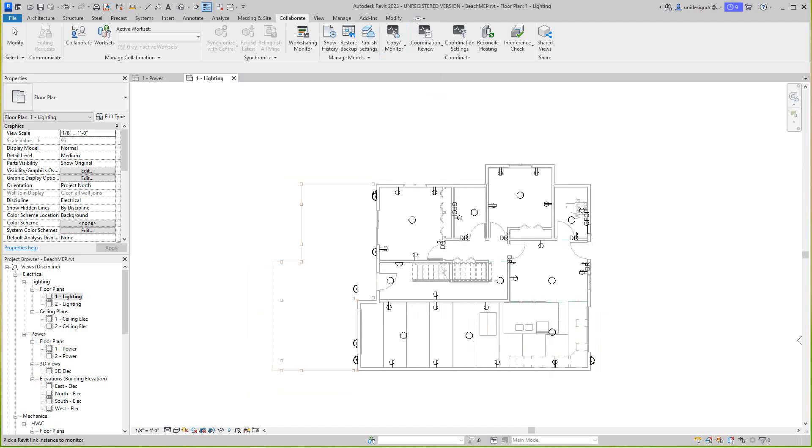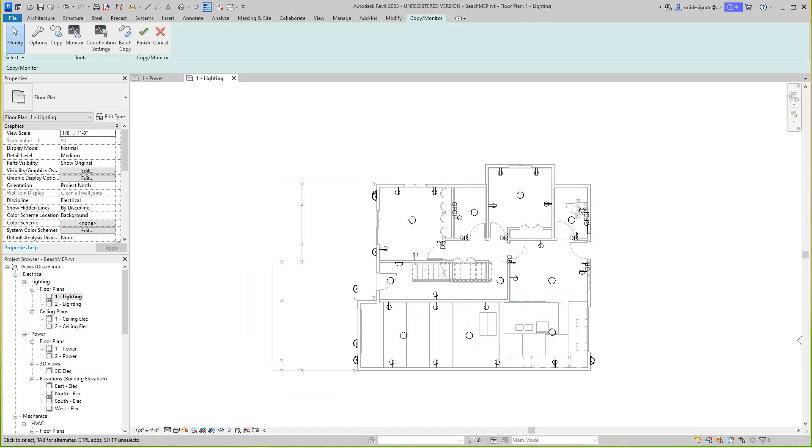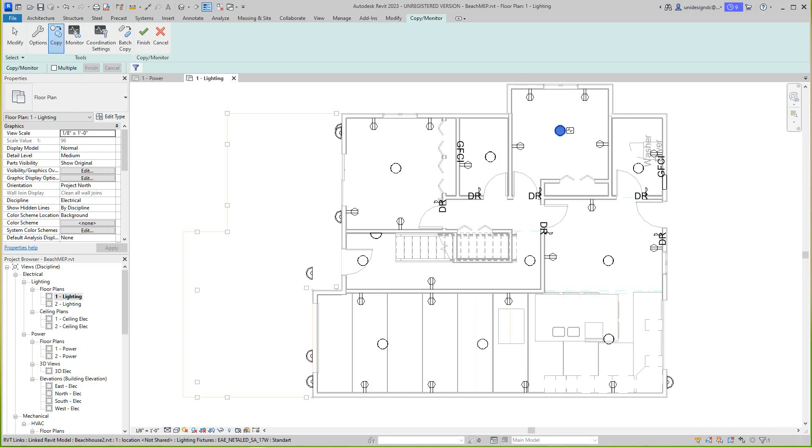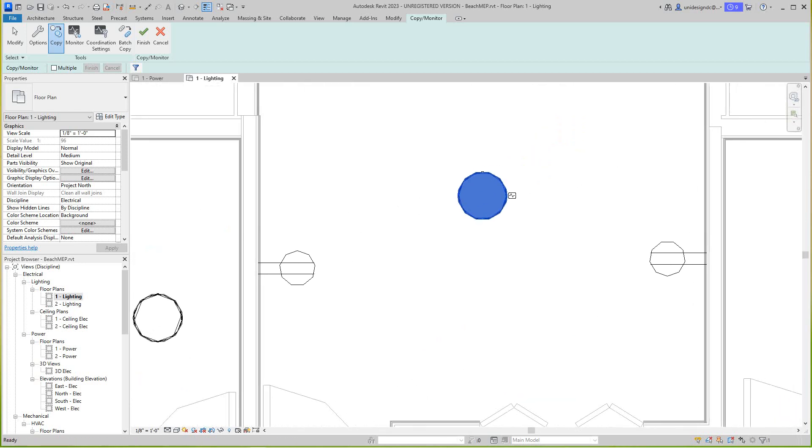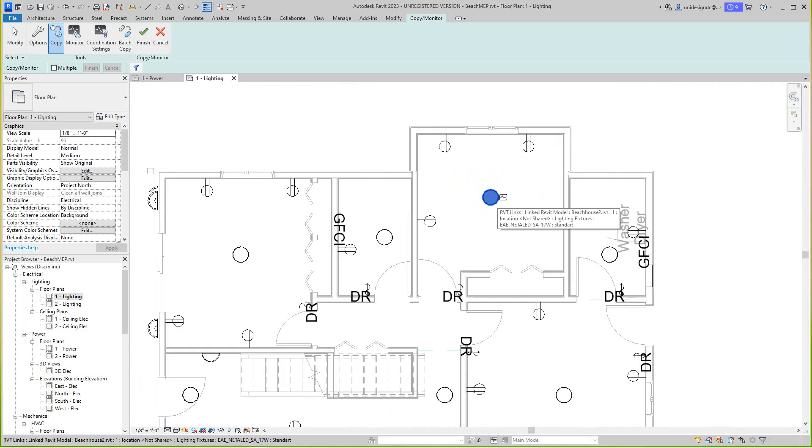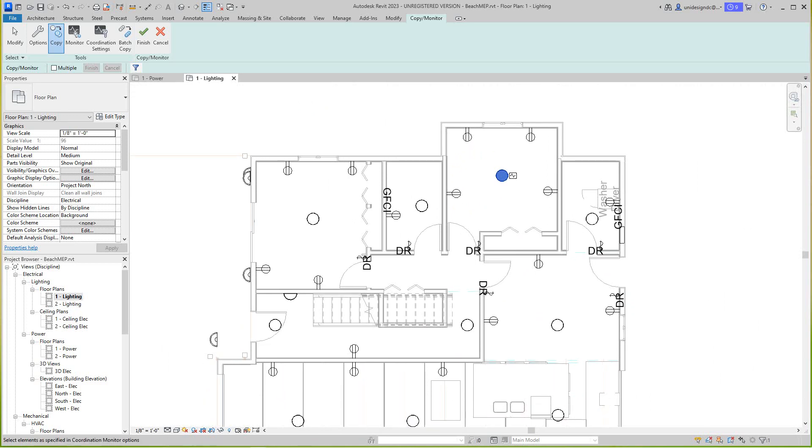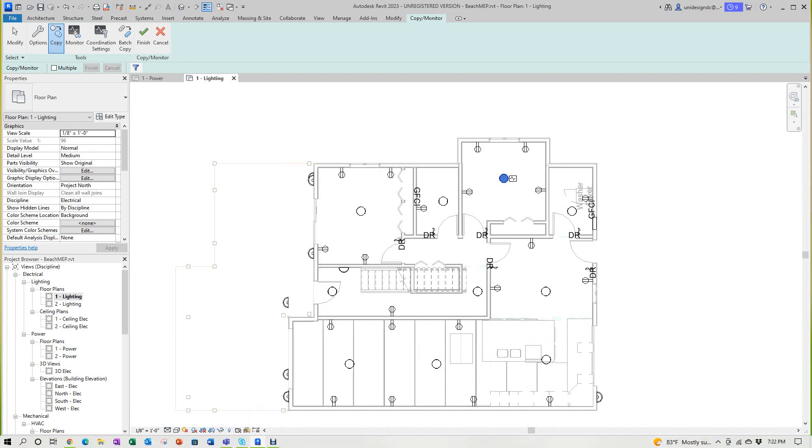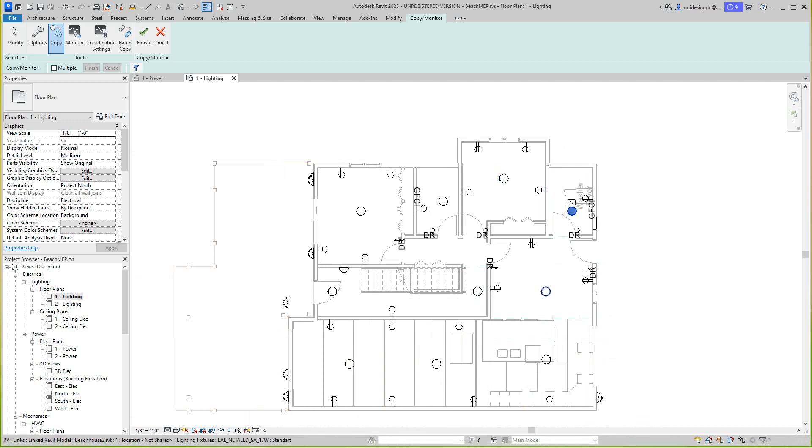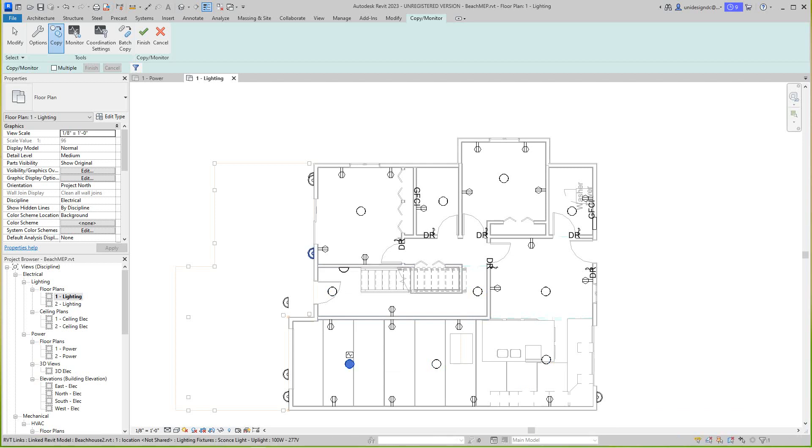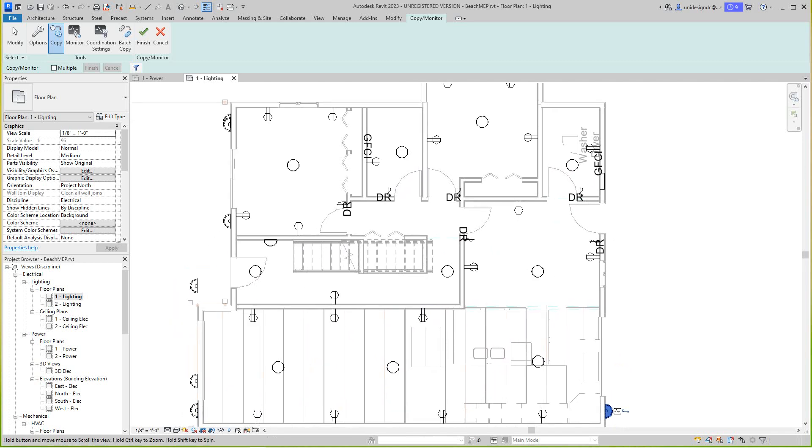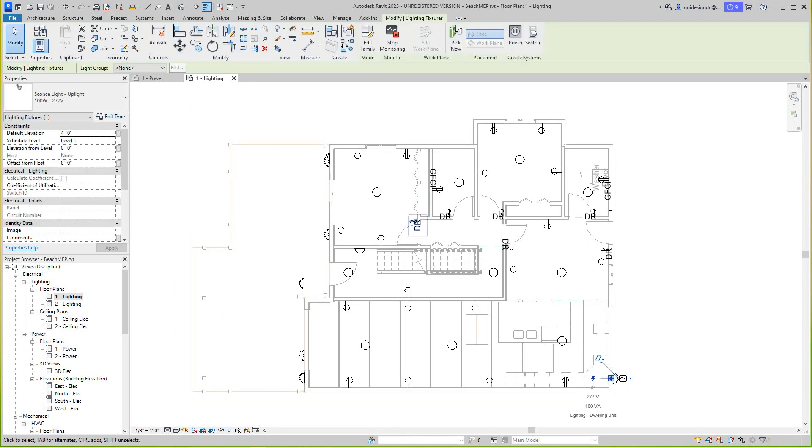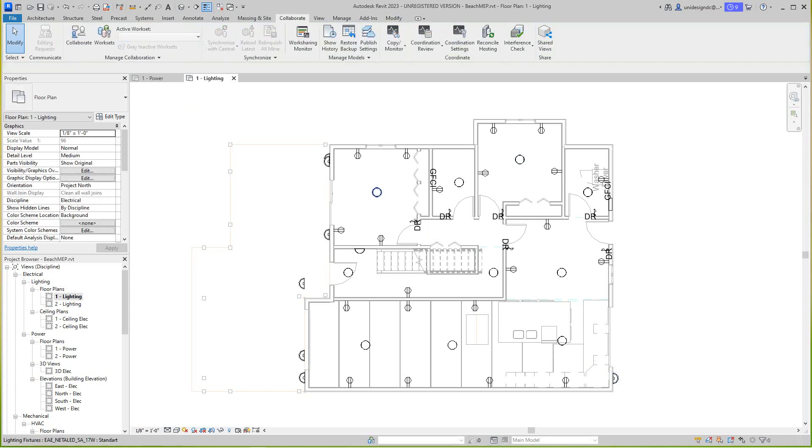Now what we'll do is just go into our copy monitor and I'm going to select this link. In this dialog box you have copy and you have these different settings, so you can copy individually. I will copy that one, that one. You notice the little check mark that means it's going to be monitored across to the architect's model. So whatever the architect does in this model, it's going to pick up across. For time's sake, I'm going to just copy them all in one by one. I want to finish that, so now we've got light fixtures in our mechanical model.